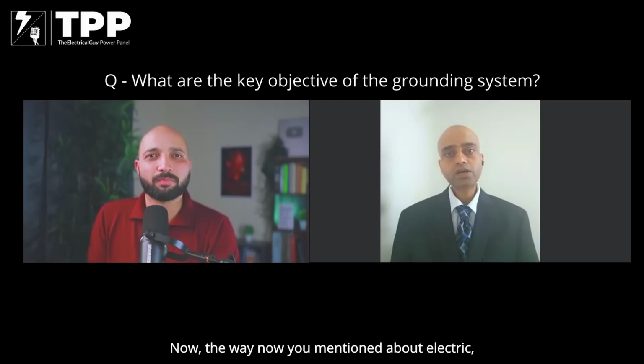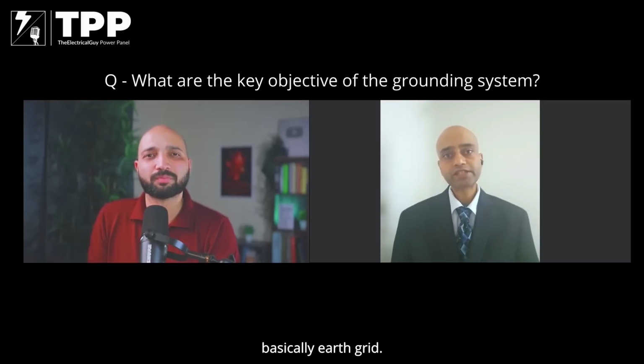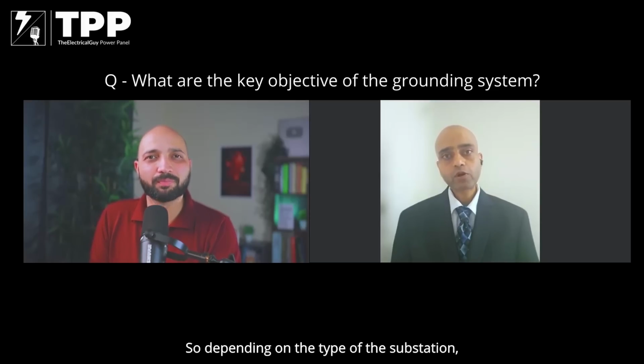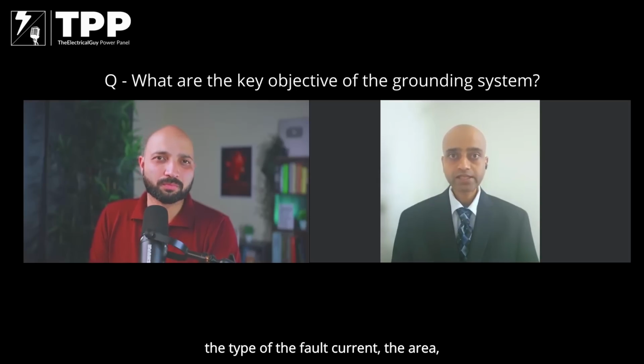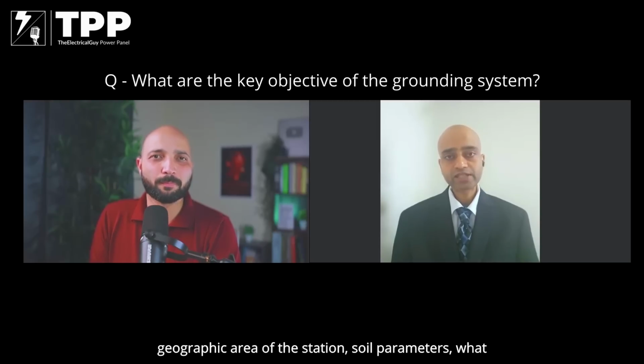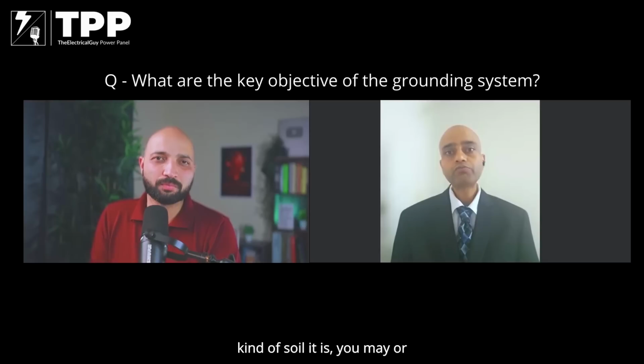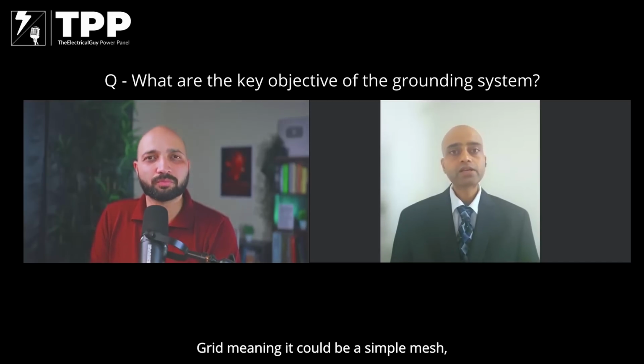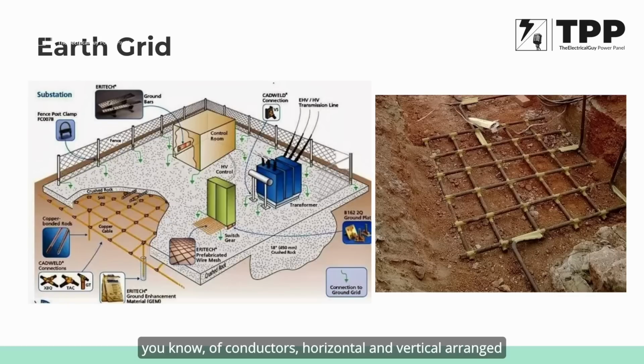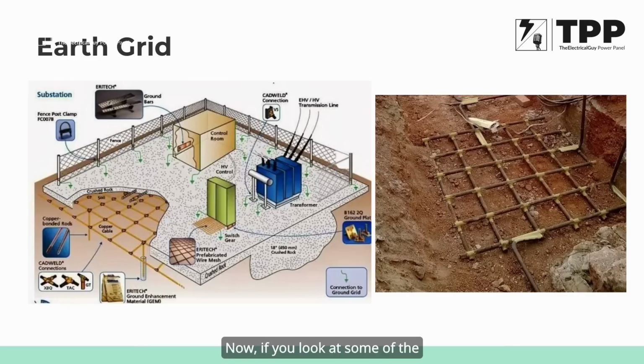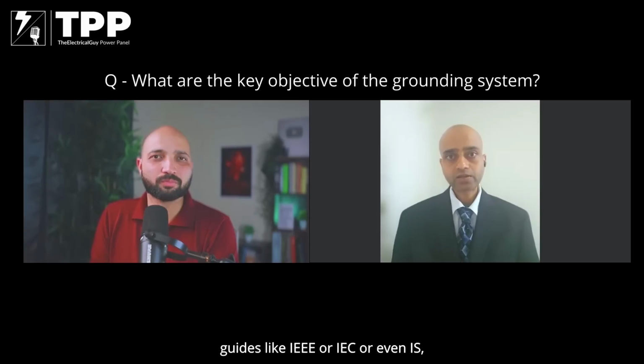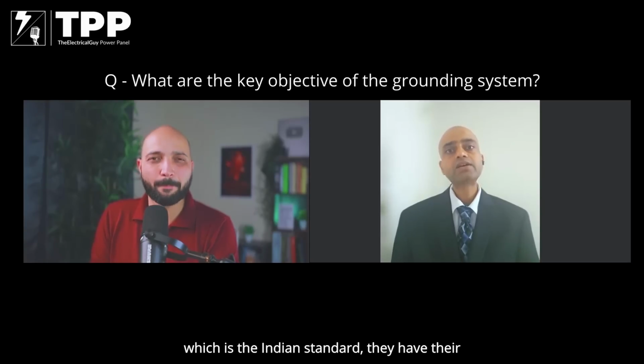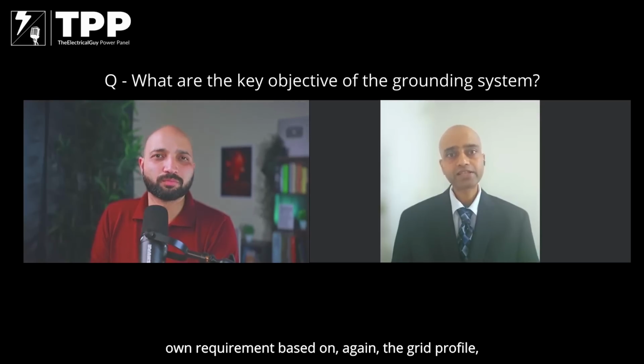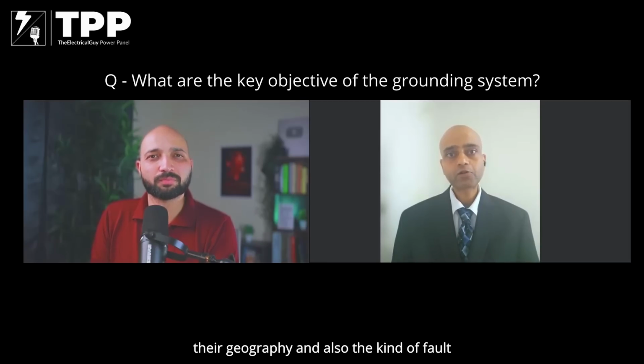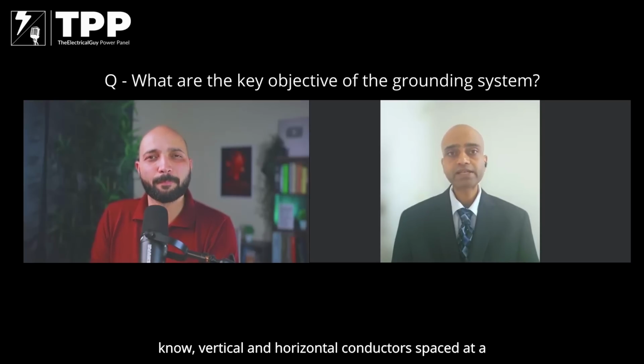Now regarding the earth grid: depending on the type of substation, the type of fault current, the geographic area of the station, and soil parameters, you may or may not require a grid. A grid could be a simple mesh of conductors, horizontal and vertical, arranged in a certain pattern. If you look at guides like IEEE, IEC, or IS, the Indian standards, they have their own requirements based on grid profile, geography, and the kind of fault currents available.